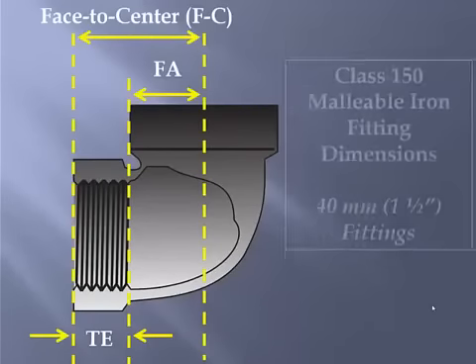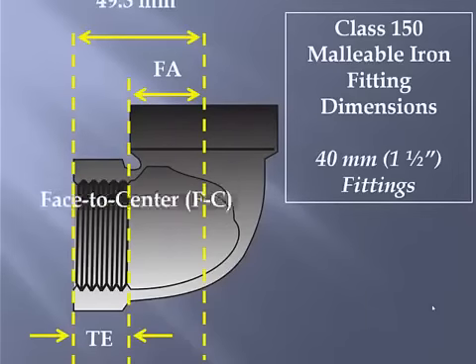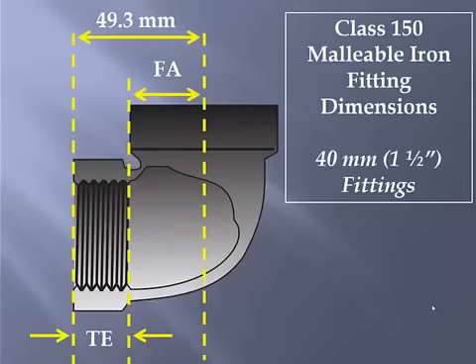So let's take a look at some actual measurements from an inch-and-a-half malleable iron fitting. We're using metric dimensions. So an inch-and-a-half malleable iron fitting is often referred to as a 40 millimeter fitting. So the face-to-center of a 40 millimeter malleable iron fitting is 49.3 millimeters. The thread engagement is 17.8 millimeters. Again, these dimensions are well published and easily referable.